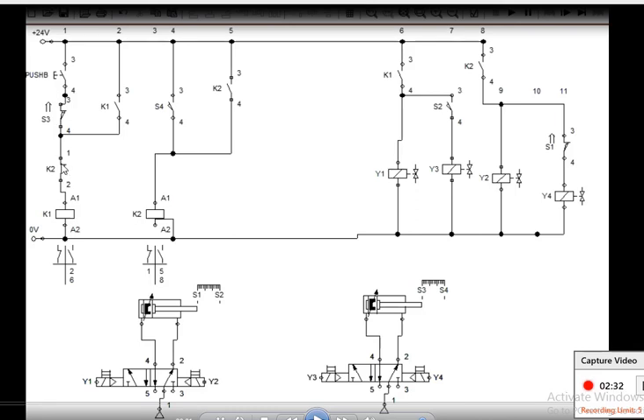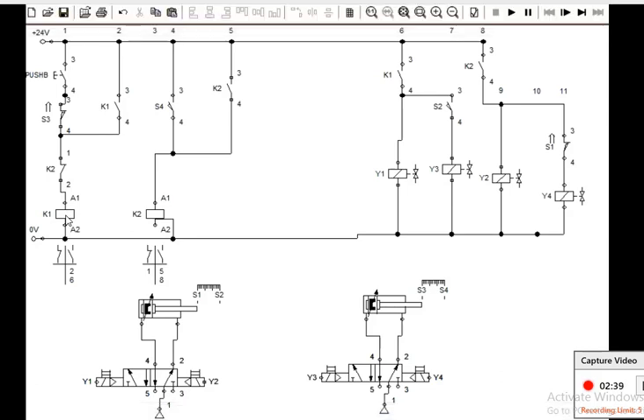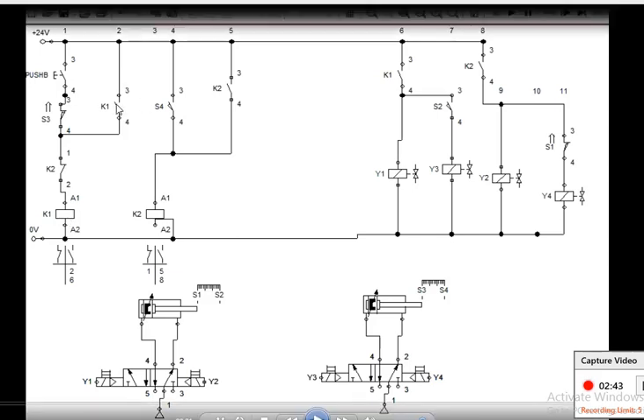Then comes the K1 coil. Since S3 is closed and the K2 normally-closed contact is also closed, the K1 coil gets current, gets actuated, and closes the K1 contact. As soon as the K1 contact closes, Y1 solenoid gets actuated and the A plus operation happens — the piston moves from S1 to S2.